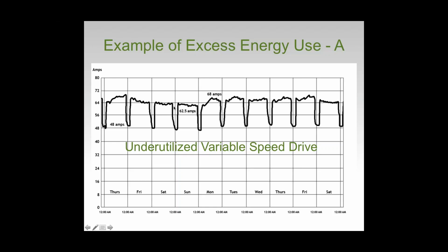And that's oftentimes something that as a facilities manager, or even as an administrator, we might look at and say, well, that's a good model of trying to reduce energy use, right? We're putting in nighttime setbacks. We're slowing the fan down on the weekend when there's less occupation. We slow down the fan a little bit compared to the weekday, and we're saving energy. Well, it's absolutely true. I won't argue with that.